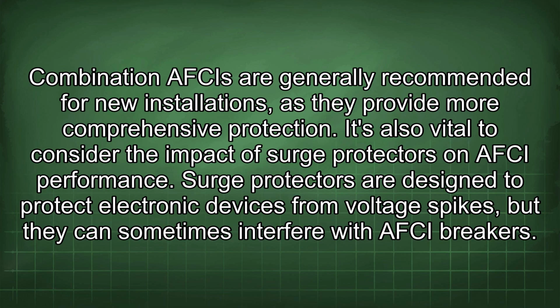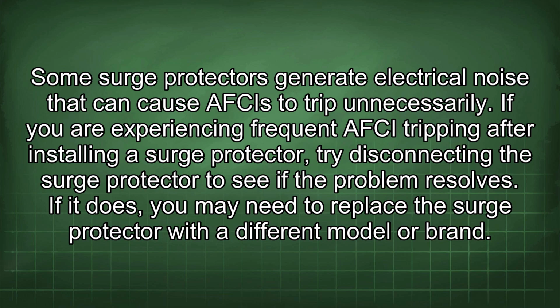It's also vital to consider the impact of surge protectors on AFCI performance. Surge protectors are designed to protect electronic devices from voltage spikes, but they can sometimes interfere with AFCI breakers. Some surge protectors generate electrical noise that can cause AFCIs to trip unnecessarily. If you are experiencing frequent AFCI tripping after installing a surge protector, try disconnecting the surge protector to see if the problem resolves. If it does, you may need to replace the surge protector with a different model or brand.